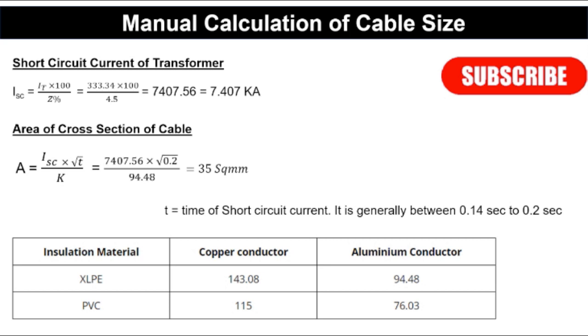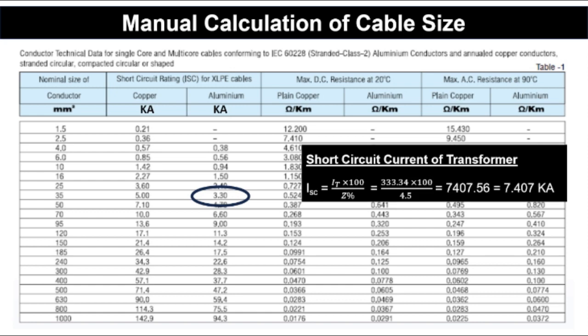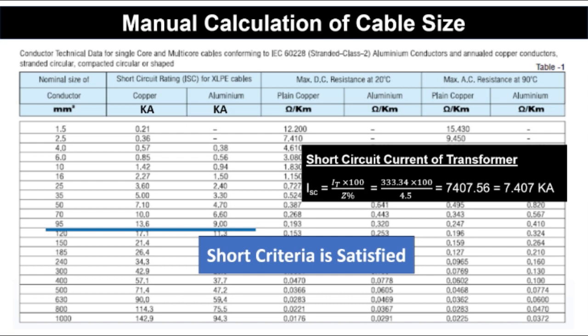Now we check whether this 35 mm² cable satisfies the short circuit current criteria using the cable catalog from KEI Industries. The 35 mm² cable has a short circuit current rating of 3.30 kilo-amperes, but our required short circuit current is 7.407 kilo-amperes — so the criteria is not satisfied. We move to the higher size: 95 mm², which has a short circuit current rating of 9 kilo-amperes. This satisfies the short circuit criteria.